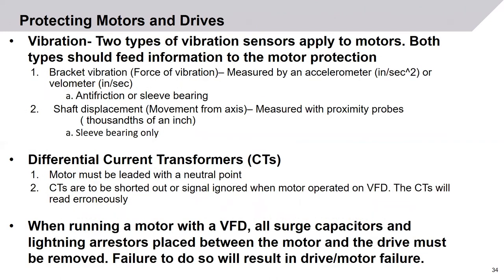There is also vibration protection. There are two types of vibration sensors that apply to motors, and both types should feed information to motor protection. Bracket vibration measures the force of the vibration, measured by an accelerometer in inches per second squared, or by a velometer in inches per second. This applies to motors with antifriction or sleeve bearings. The other protection required is shaft displacement — actual movement about an axis due to vibration — measured with proximity probes in thousandths of an inch. Due to construction, this applies to sleeve bearings only.